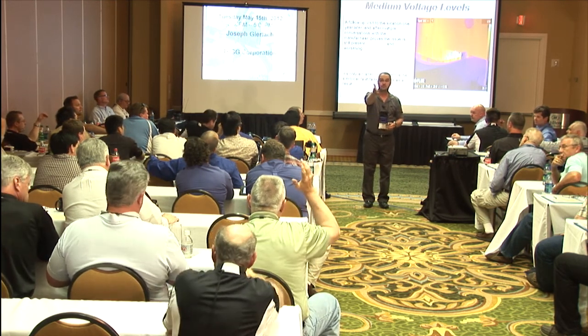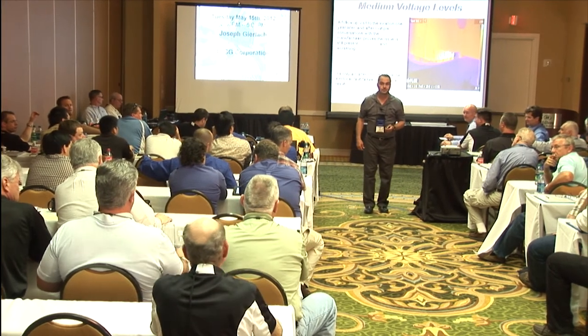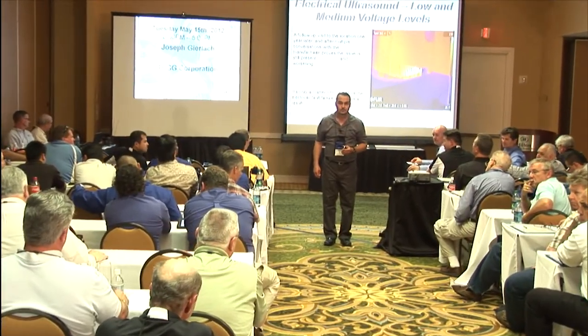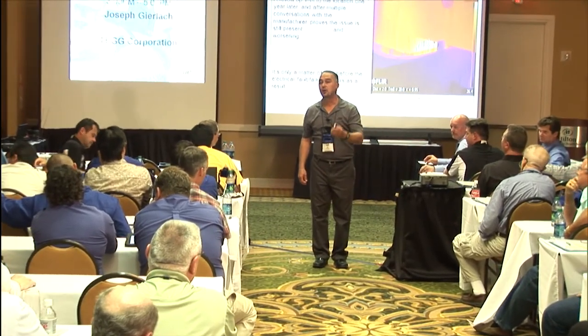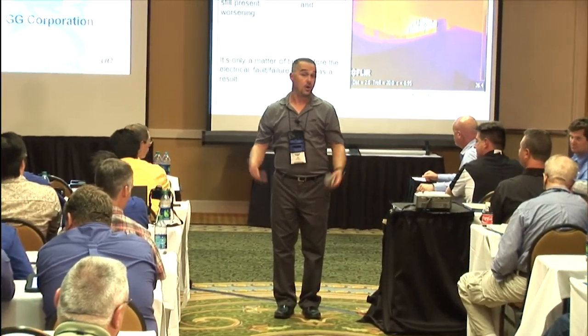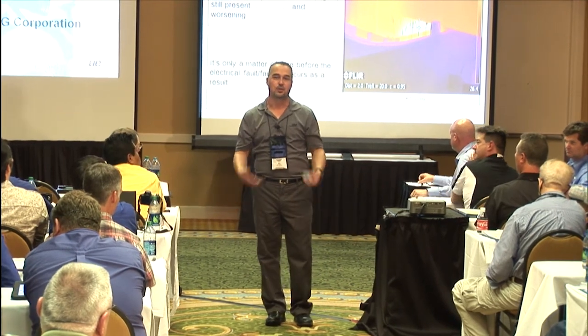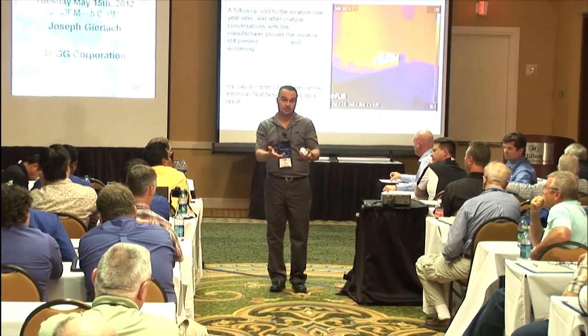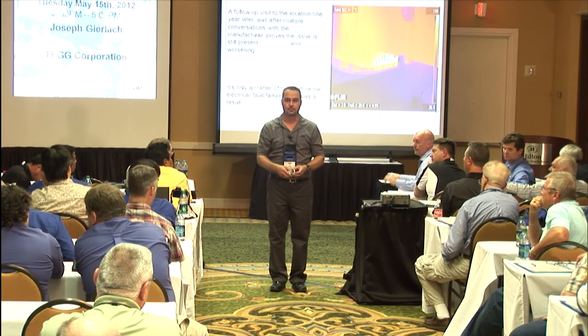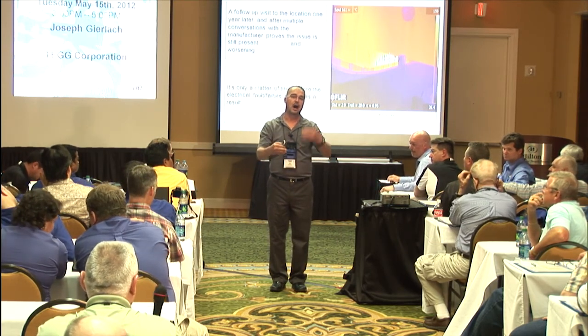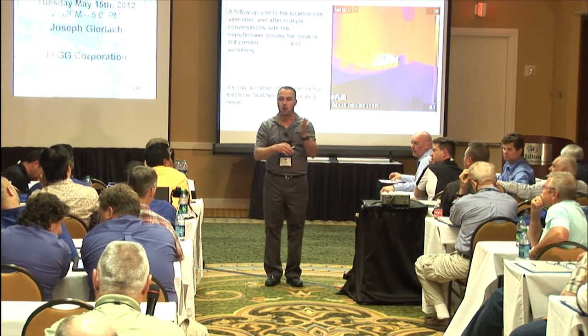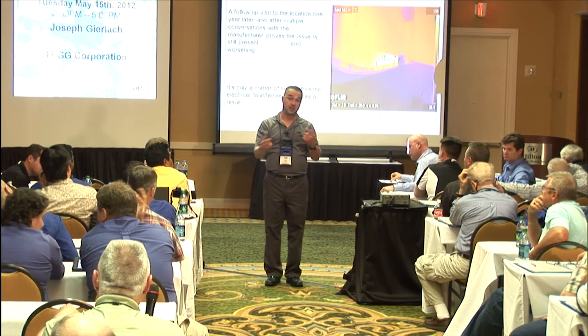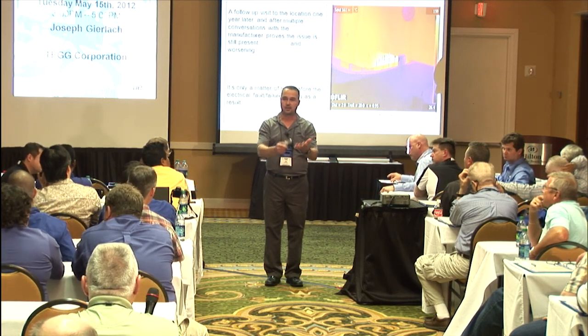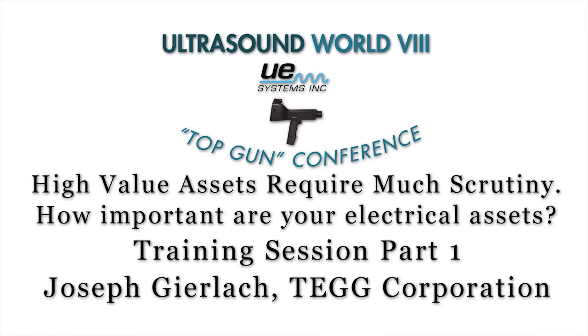Does that make sense? Yes sir — would that be seen in, say, an electrical motor that's closest to the source? If it's on a drive, possibly. You think about a variable speed drive, it's basically a rectifier, right? And that rectifier produces harmonics that go back on the system. So the closer you get to these loads, the higher the levels of harmonics you'll see. It's a similar concept in the FFT, it's multiples of 60. And then depending on the technology you're using — diodes, SCRs, IGBTs — that will determine what frequencies are produced. Is it single phase, is it three phase?